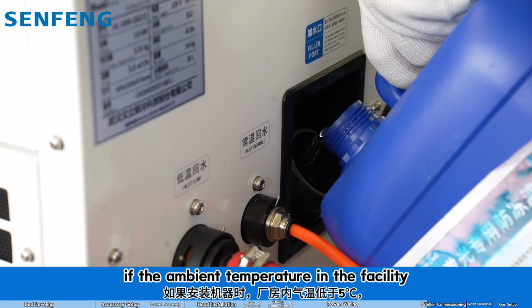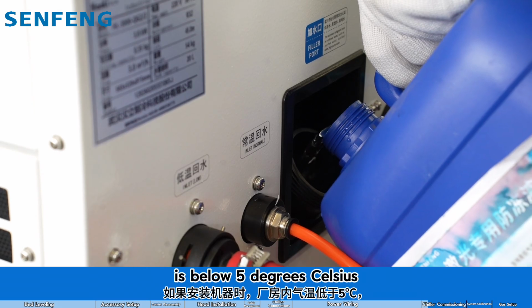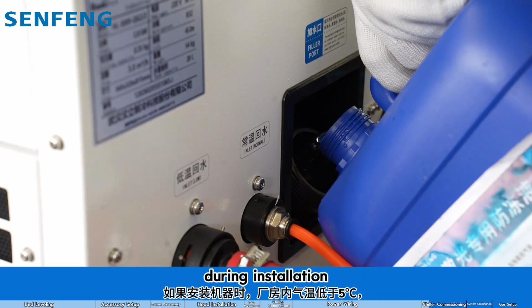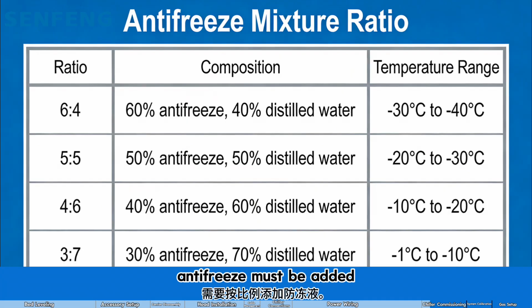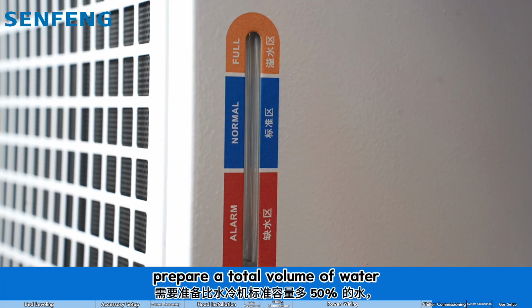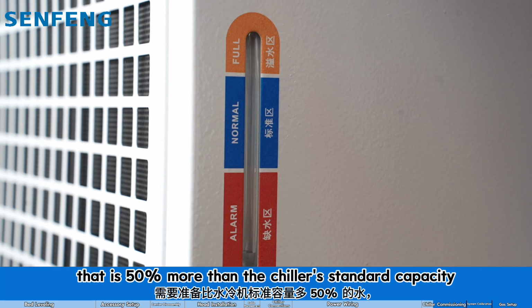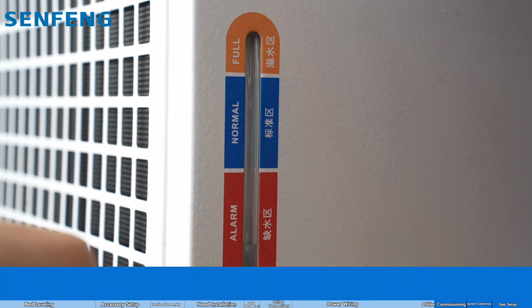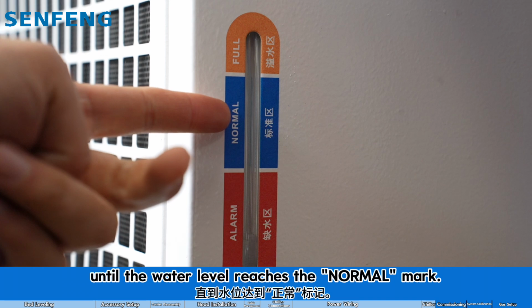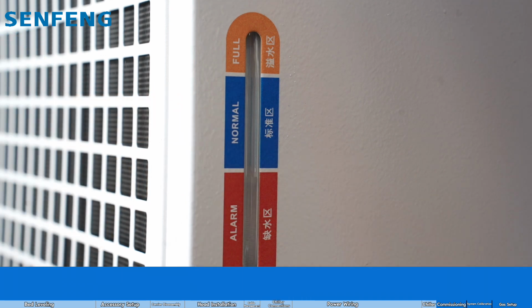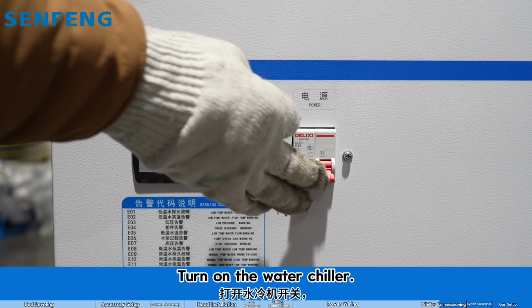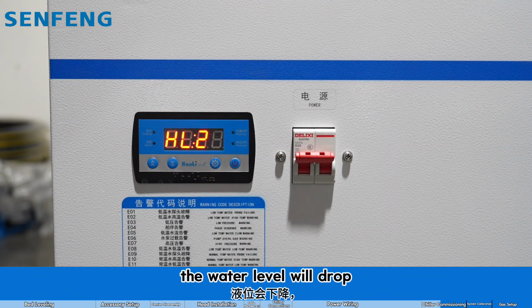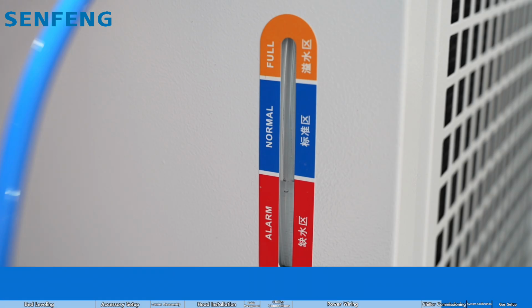Note: if the ambient temperature in the facility is below 5 degrees Celsius during installation, antifreeze must be added according to the specified ratio. Prepare a total volume of water that is 50% more than the chiller's standard capacity. Fill the tank until the water level reaches the normal mark. Turn on the water chiller. The water level will drop as it fills the external lines.